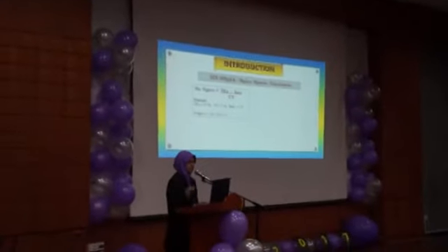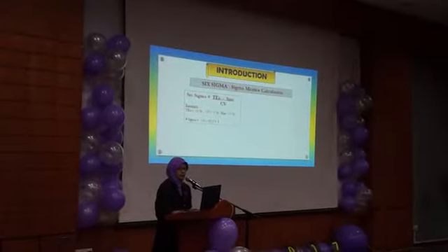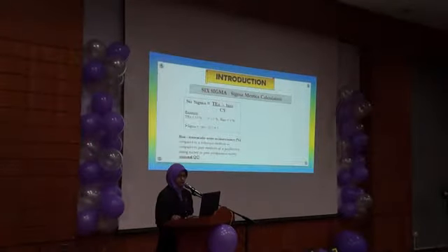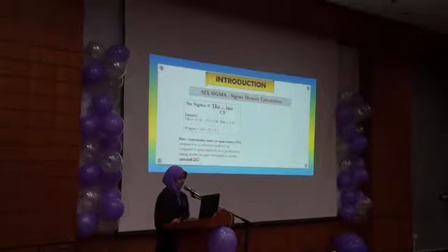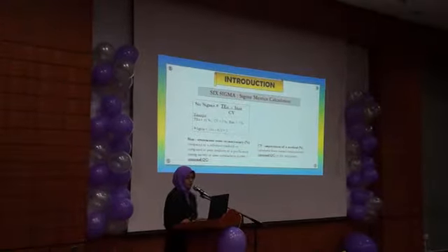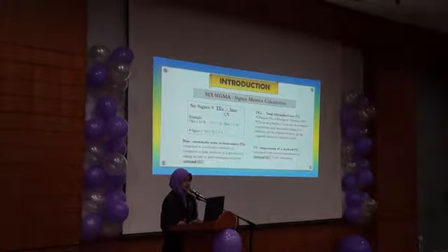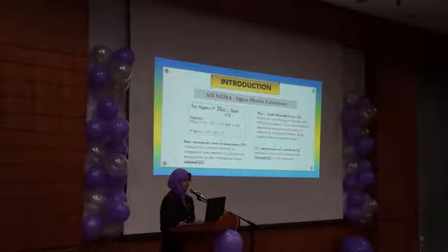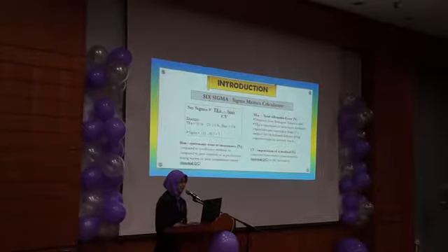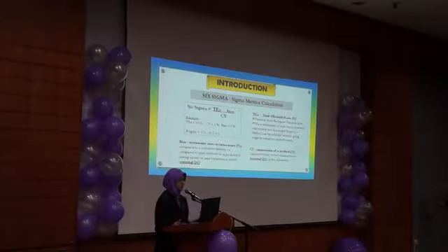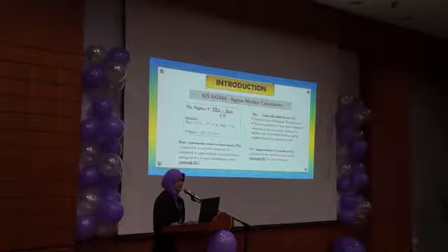For Sigma metric calculation, for the laboratory, the Sigma metric is calculated using this formula: TEa minus bias over CV. For different fields, there are different ways to calculate the Sigma metric. In the formula, bias is the systematic error, which we can get from external QC. CV, the imprecision of the method, we can get from our internal QC. And TEa, or total allowable error, we can obtain from the biological variation table, which is available online. TEa is the expression of how much bias and imprecision of a method can be tolerated without giving a negative impact to a patient's result.